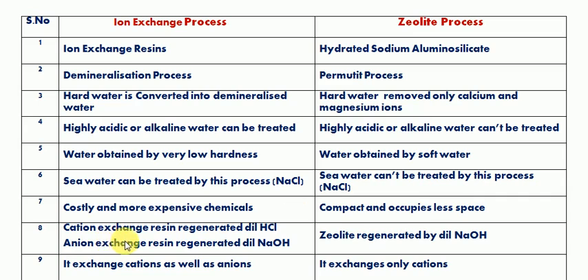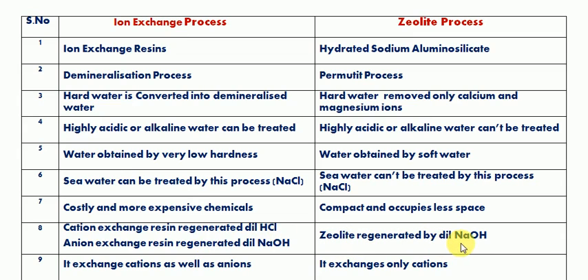In the ion exchange process, cationic exchange resins are used along with anionic exchange resins. Cationic exchange resins are regenerated using diluted hydrochloric acid, and anionic exchange resins are regenerated using diluted sodium hydroxide. But in the zeolite process, regeneration is done by diluted sodium chloride solution.